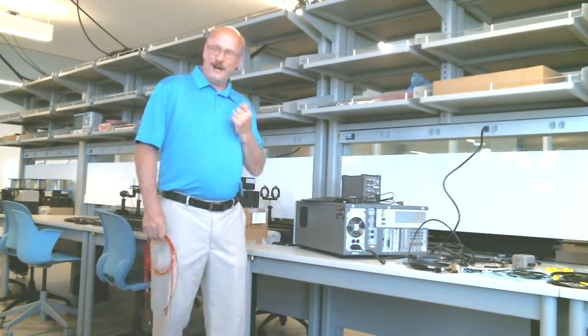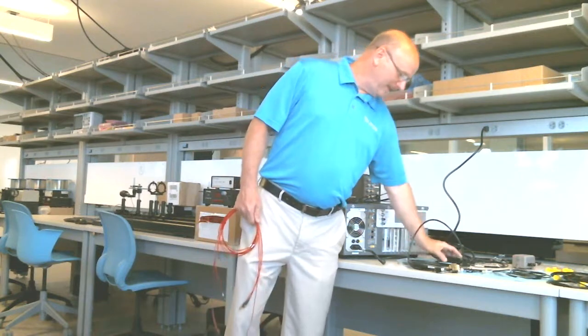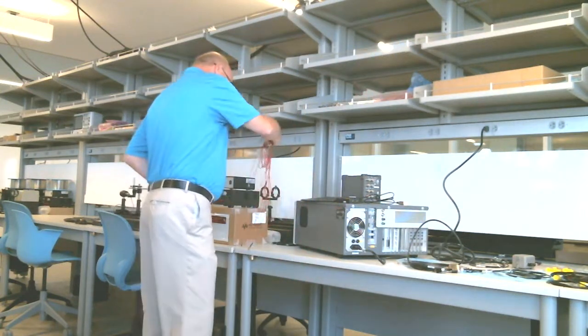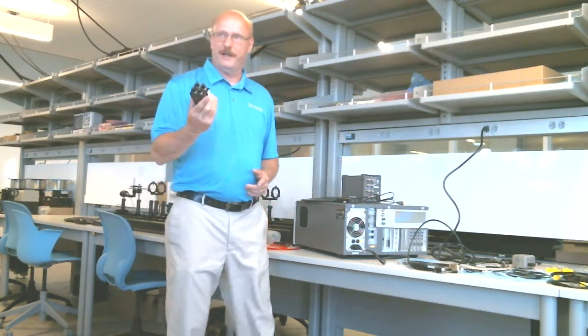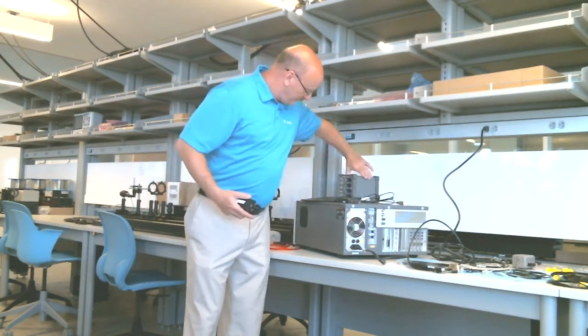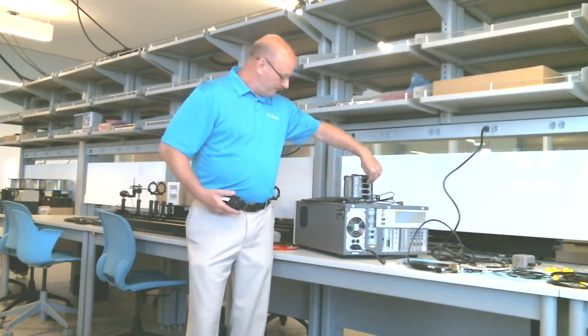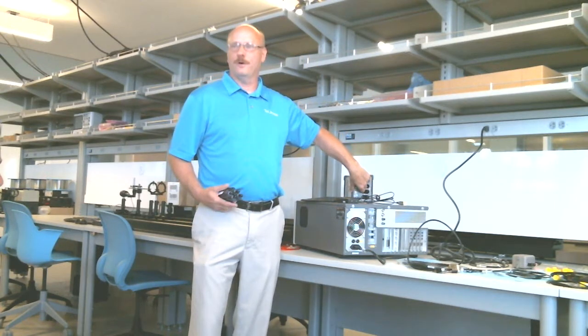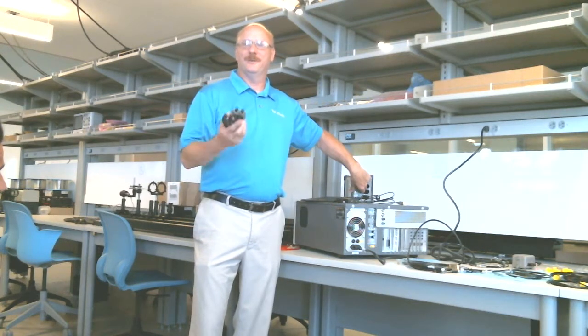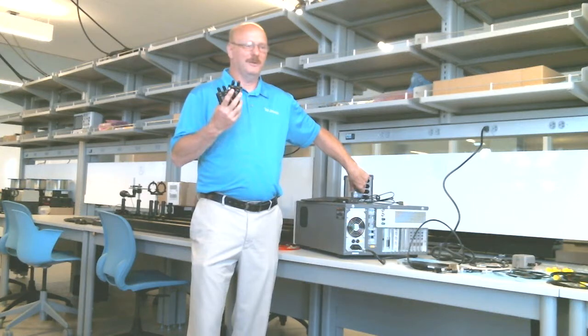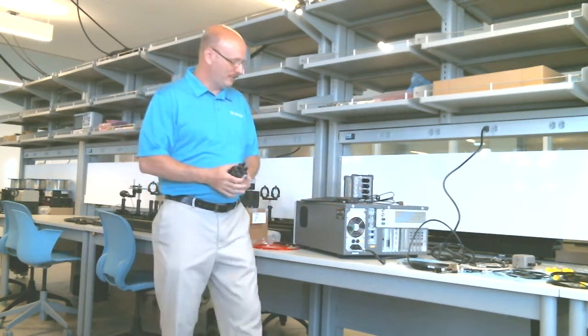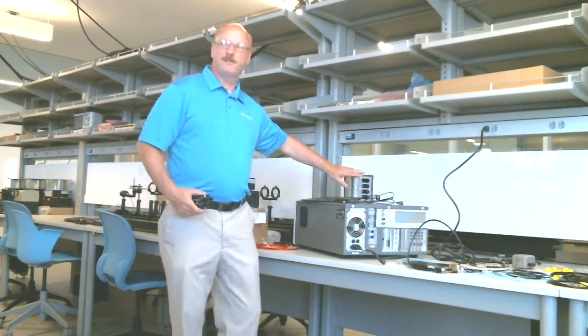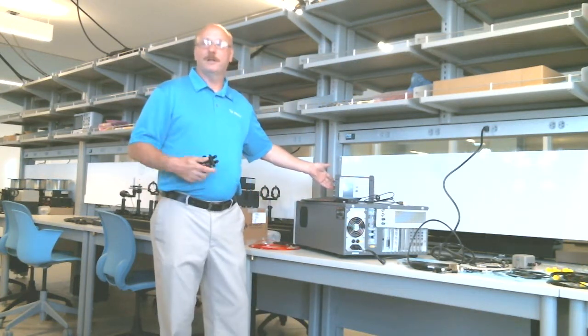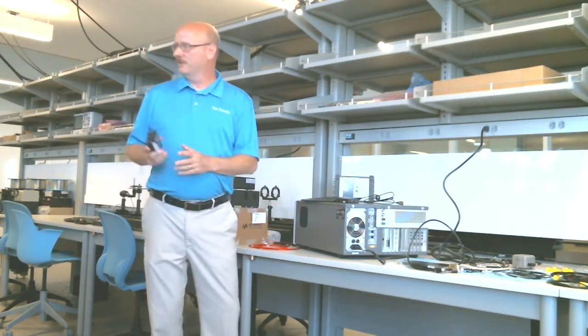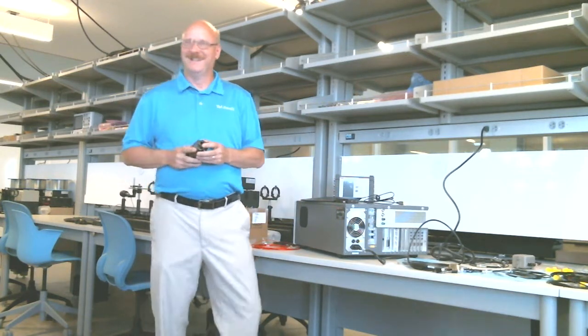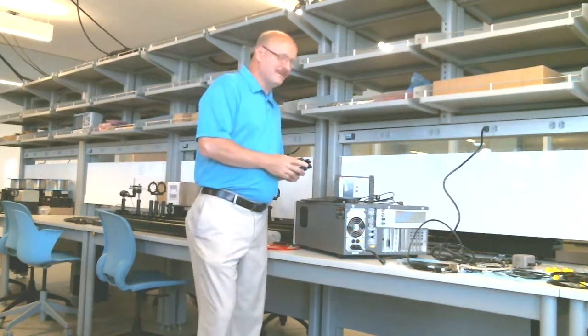Okay. Now I discovered a problem when we got here. You've got 2 of these pass-throughs. So these are used in a case where you don't have preamps. See, the preamp's going to go inside SMU1 slot down here. But you don't have preamps for 2, 3, and 4. So you'd use these. Now we got 2. We need 1 more of these. So we're going to have to get you another one of these. So these allow you to bring the triax from the SMUs into this box so that you can get them to the output. We're only going to be able to bring 3 out until we get you another one of these. Jen's going to take care of that, right? Didn't think about that when you guys placed the order. That's my fault. I should have caught that.